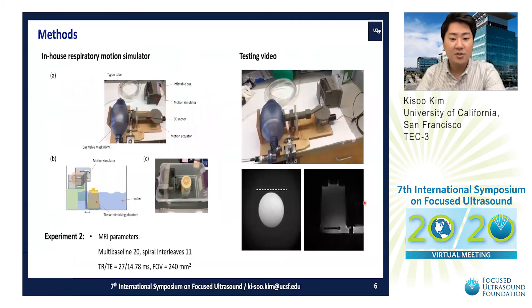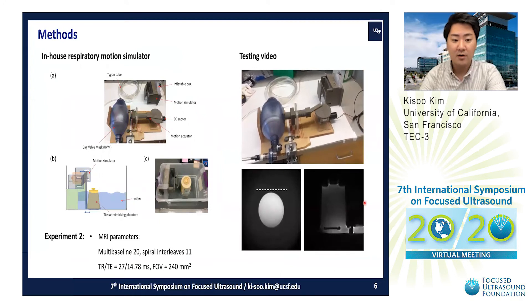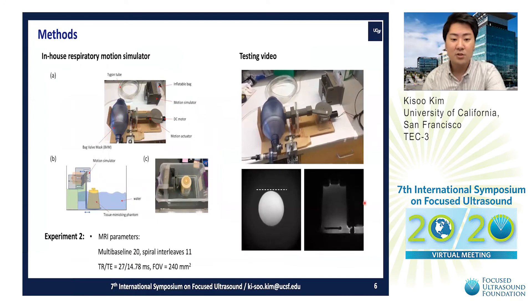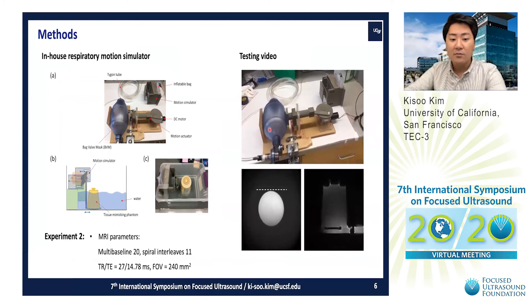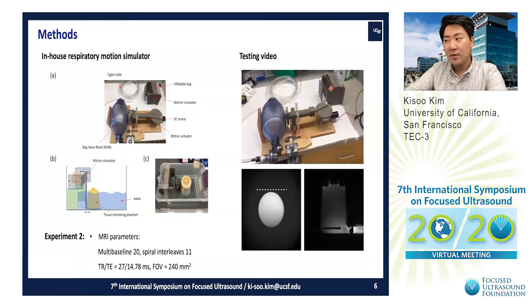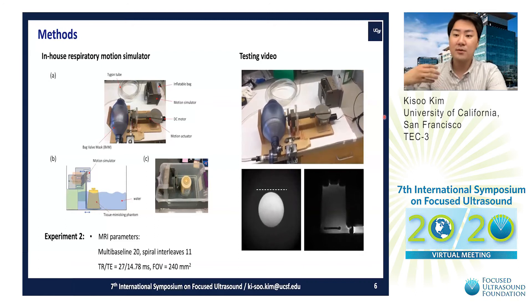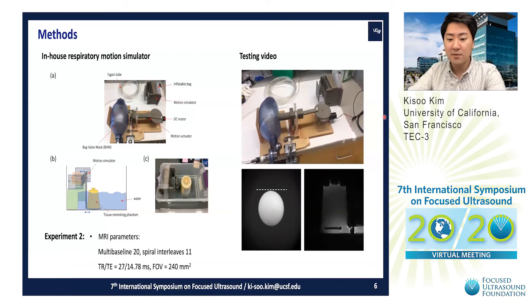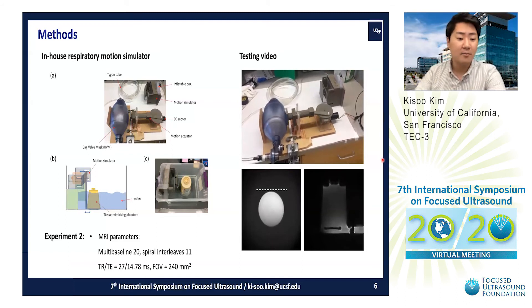For the second validation, we developed a low-cost MR-compatible motion simulator. A homemade motion actuator can control pressure in a balloon bag coupled via tubing in a motion simulator, which is placed in the MRI scanner. It can push and pull our tissue-mimicking phantom in the MRI. We ran a non-heating experiment with these MRI parameters.